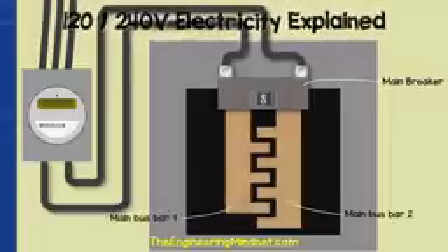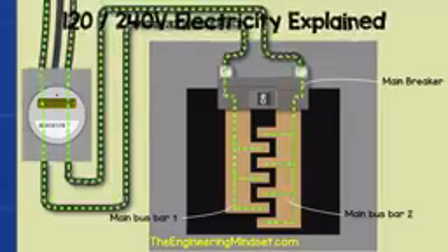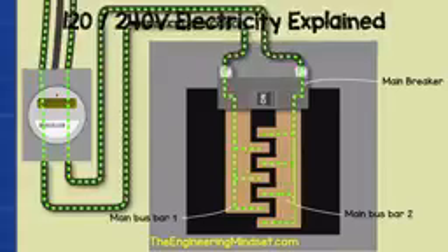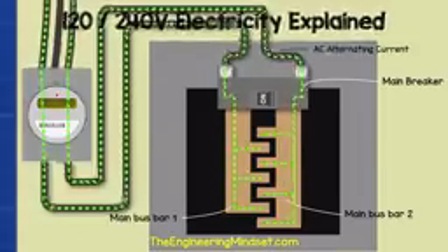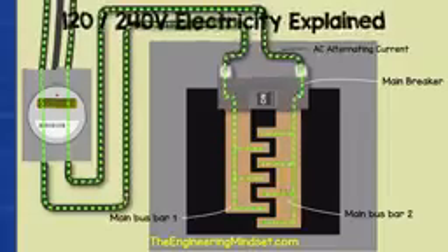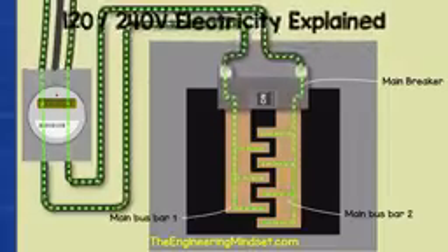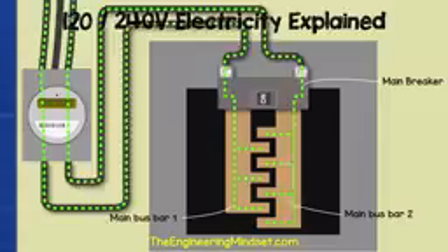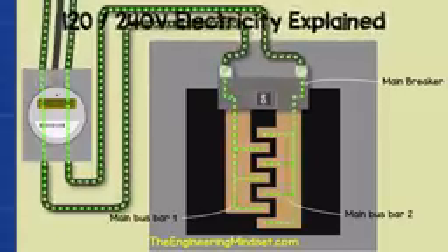These are basically exposed metal sheets which carry electricity to the circuit breakers. Notice I've shown the current flowing backwards and forwards. That's because this is AC or alternating current. These bus bars as well as the lugs are not insulated, they are live or hot. The main breaker can be manually flipped to cut the power to everything downstream of the main breaker.